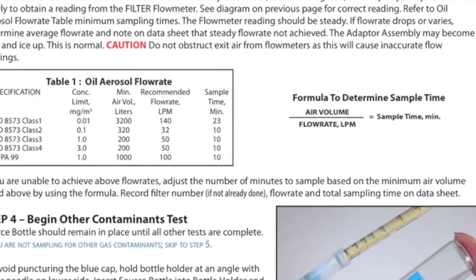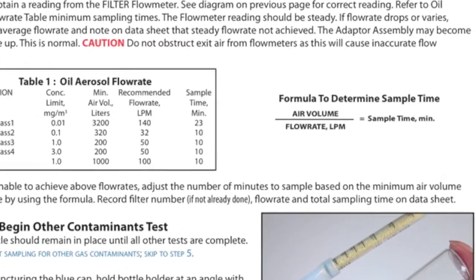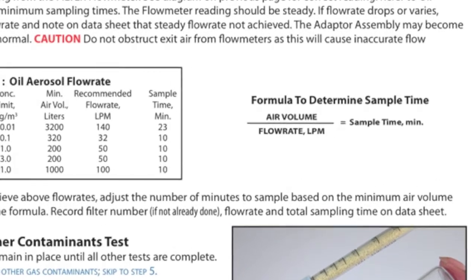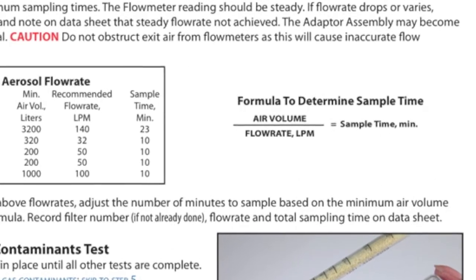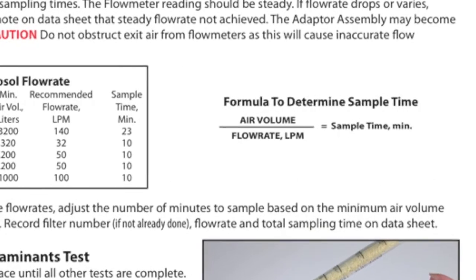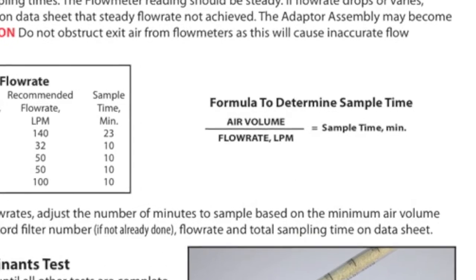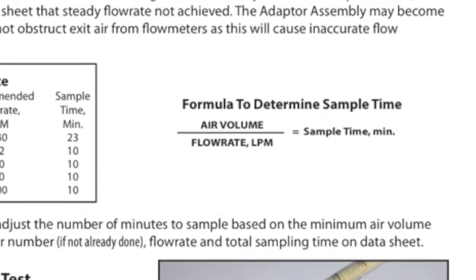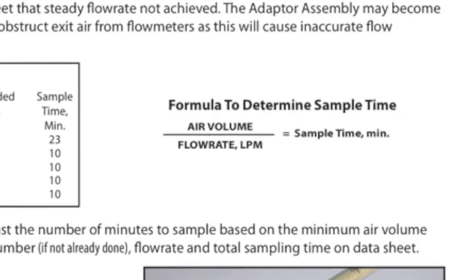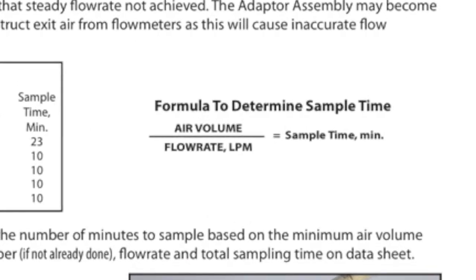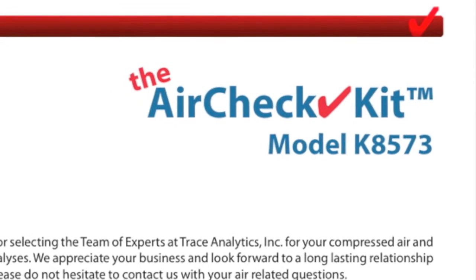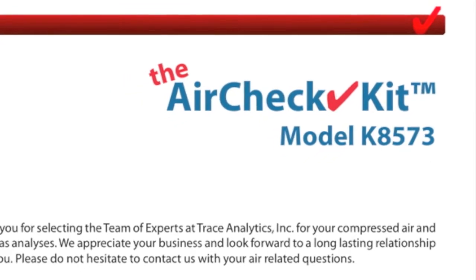If you're unable to obtain the recommended flow rate, then take the required air volume from table one, divide it by the flow rate that you can obtain, and this will give you the correct sample time in minutes. The formula is noted in the sampling instructions.